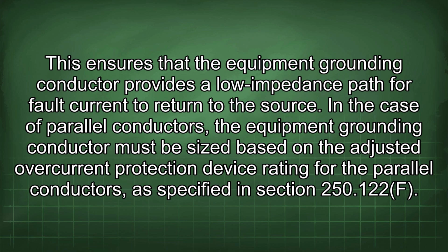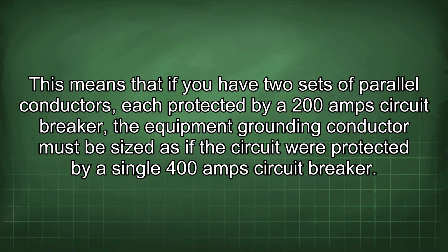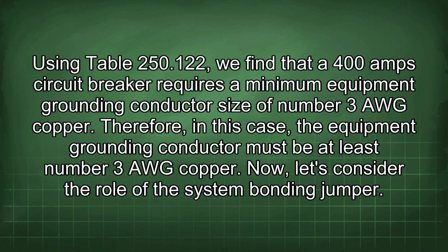In the case of parallel conductors, the equipment grounding conductor must be sized based on the adjusted overcurrent protection device rating for the parallel conductors, as specified in section 250.122(F). This means that if you have two sets of parallel conductors, each protected by a 200 amp circuit breaker, the equipment grounding conductor must be sized as if the circuit were protected by a single 400 amp circuit breaker. Using table 250.122, we find that a 400 amp circuit breaker requires a minimum equipment grounding conductor size of number 3 AWG copper. Therefore, in this case, the equipment grounding conductor must be at least number 3 AWG copper.